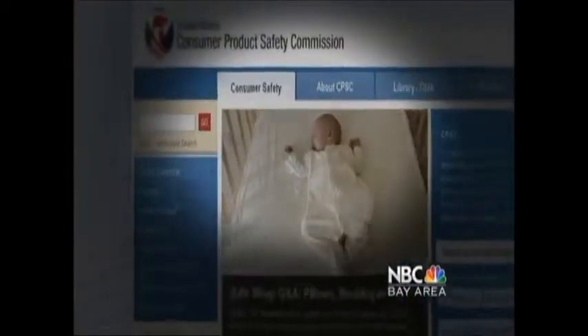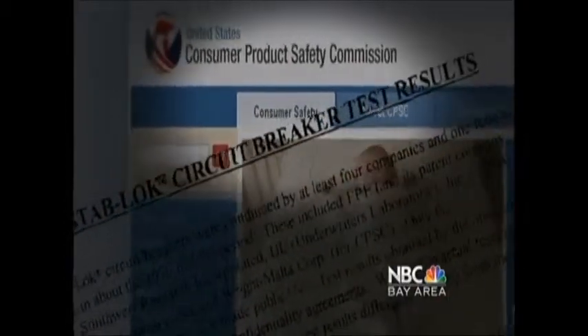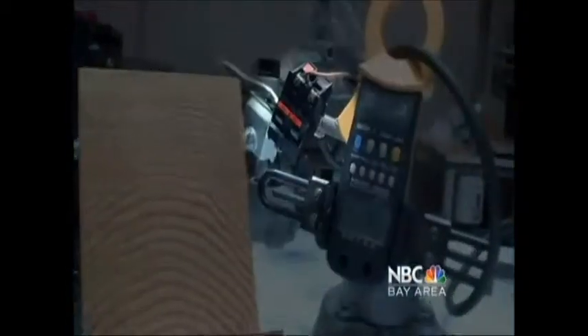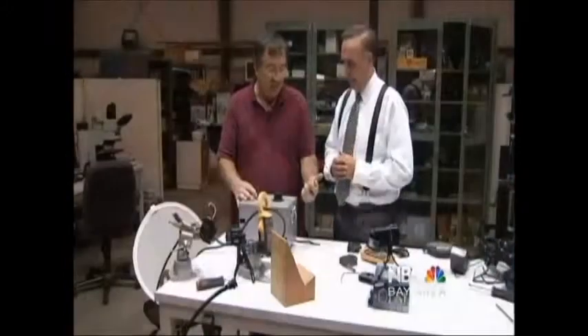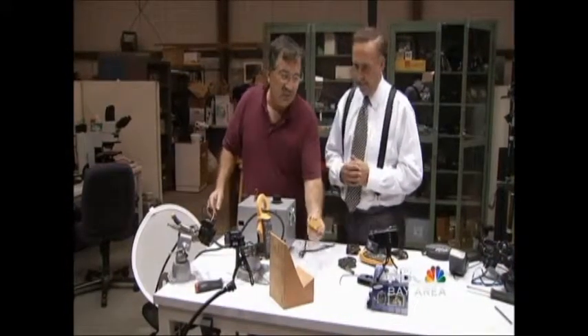Ehrenstein says tests by the Consumer Product Safety Commission and a number of other credible labs all proved Federal Pacific breakers are not reliable. This is a Federal Pacific breaker. So how does it fail? Watch closely. We had a Federal Pacific circuit breaker tested at this lab in Berkeley. We've started. It's a 60 amp breaker, the same as you find in many homes. We've doubled the current it's rated to handle.